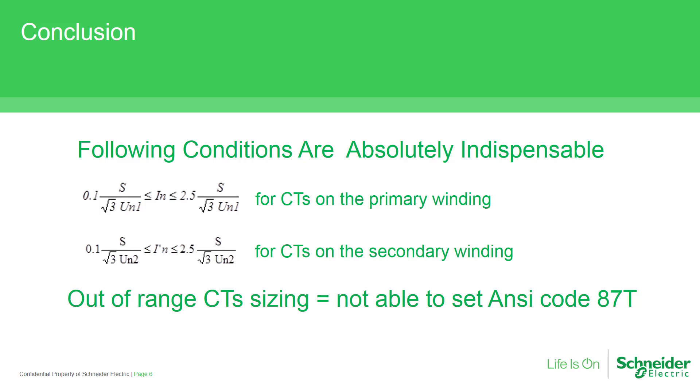Jumping to conclusion, meeting following conditions are absolutely indispensable for current CT sizing in transformer differential application for SEPAM series 80 protection relays. Out of range CT sizing means we won't be able to set transformer differential protection.